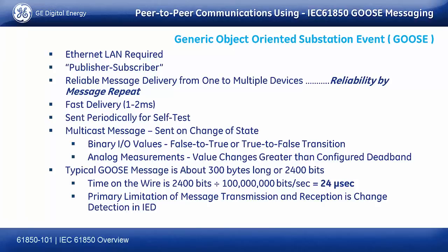And we use it for GOOSE, because GOOSE is a simple event. It's a multicast message. GOOSE stands for Generic Object-Oriented Substation Event, right? So what this means is a GOOSE message is only published, and uses a publish-subscribe model. It is only published when one of the data set items changes state, okay? And I'll talk about changing state, right? And I'm going to publish to the network as a multicast message, so any device subscribing to that GOOSE message can understand it's there and get the data, right?